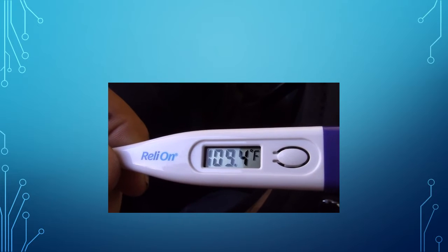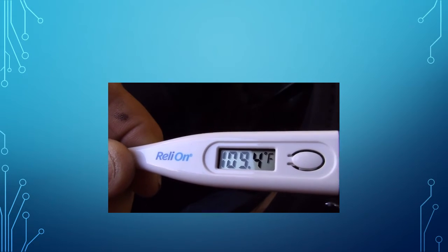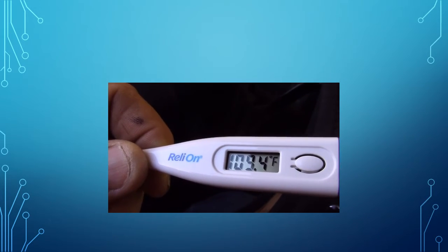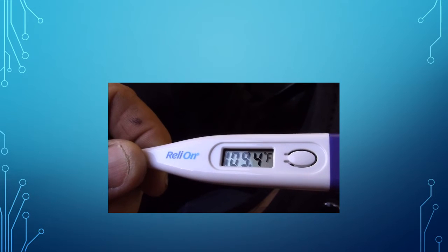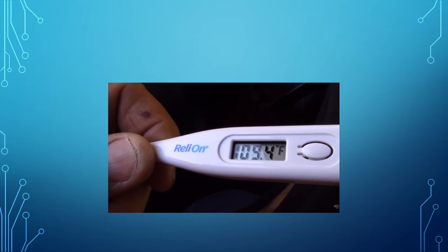Okay, so I just got back to the truck where I could read this because outside the sun glare is so bad I can't tell what I'm reading. So today, the temperature is 99 degrees, according to my truck. The transformer on the outside today is 109.4. So yesterday it was 110, so we're going to add 11 to that. So the thermometer would have said 120.4, which is Fahrenheit, and the transformer is rated at 40 degrees centigrade. So we're going to show you what the conversion is on that.